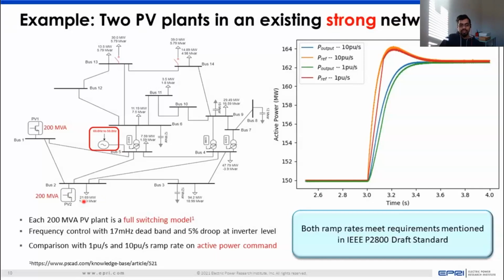So all of the full-blown details of the control which is used in this plant is actually available at this link here for folks who want to take a deeper dive into it. And we see that for the two different ramp rate values, 1 per unit per second and 10 per unit per second, there is a noticeable change: with 1 per unit per second, you can see it being clamped to 1 per unit per second here in the red curve with respect to the reference command, whereas the orange curve with respect to the 10 per unit per second, the reference command has a more noticeable exponential kind of response.